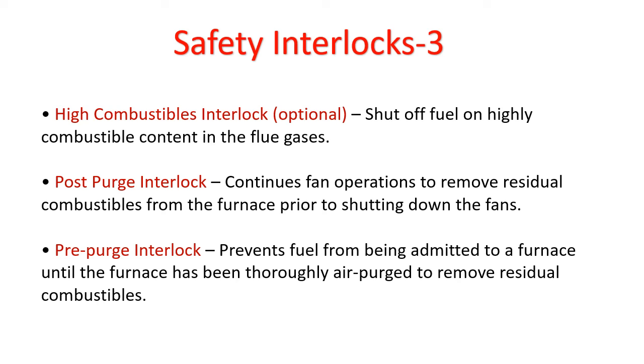Post purge and pre purge are two different interlocks. The pre purge interlock prevents fuel from being admitted to a furnace until the furnace has been thoroughly air purged to remove the residual combustibles. And then there is the post purge interlock, which continues the fan operation to remove the residual combustibles from the furnace prior to shutting down the fans.